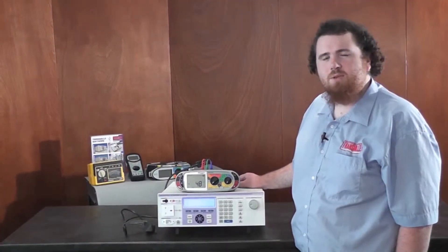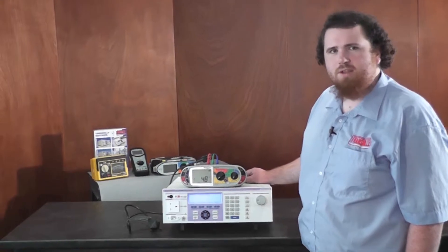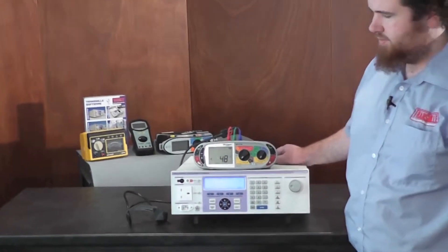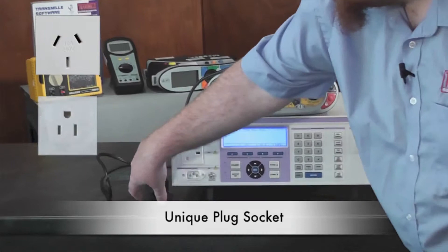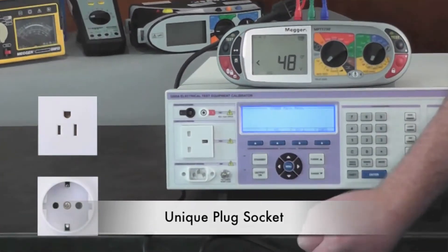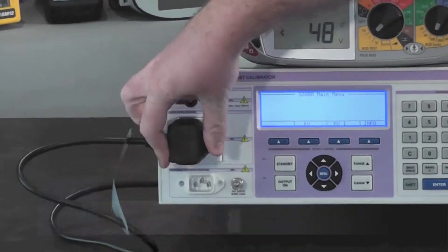Calibrating RCD testers with the 3200A is quick and safe. Using Transmille's unique plug socket on the front of the 3200, testers simply plug in.